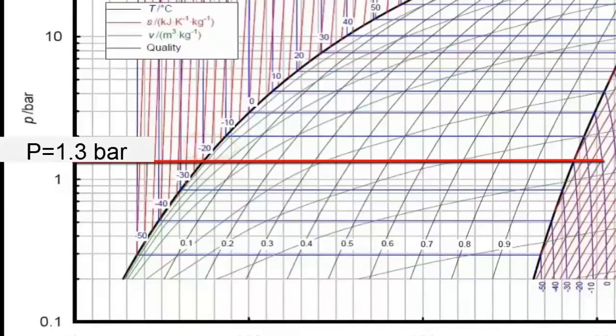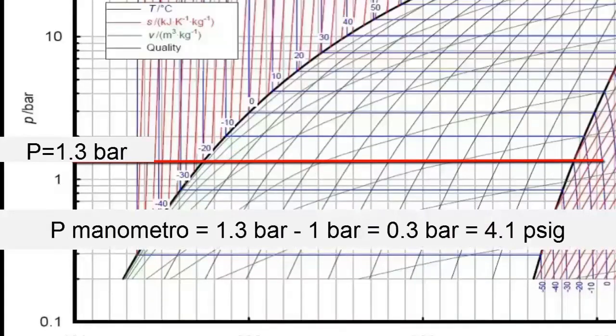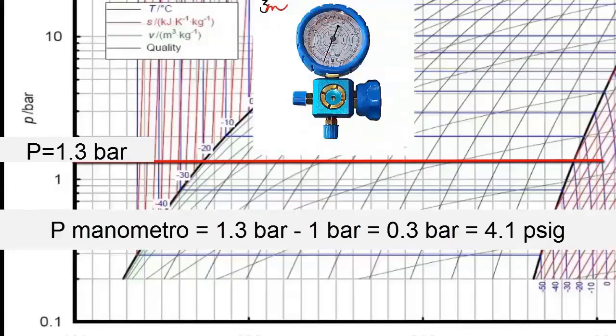To find the pressure that the manometer should read, we must subtract the atmospheric pressure from the absolute pressure of the diagram. By subtracting 1.3 bars minus 1 bar from the atmospheric pressure, we have a manometer pressure of 0.3 bars. The blue or low pressure gauge should read 0.3 bars or the equivalent of 4.1 psi.